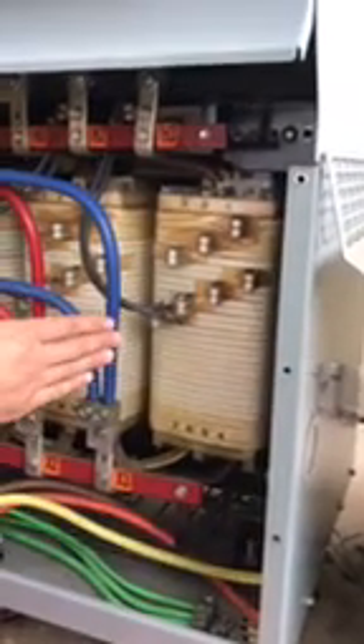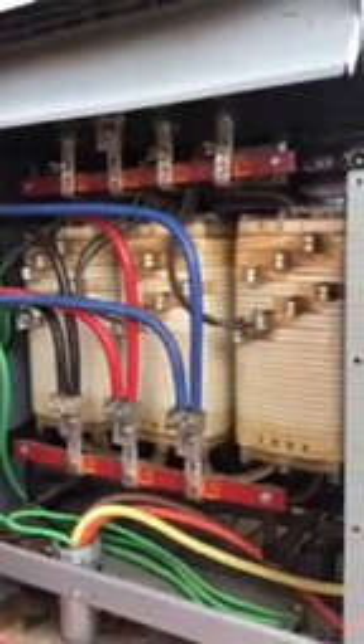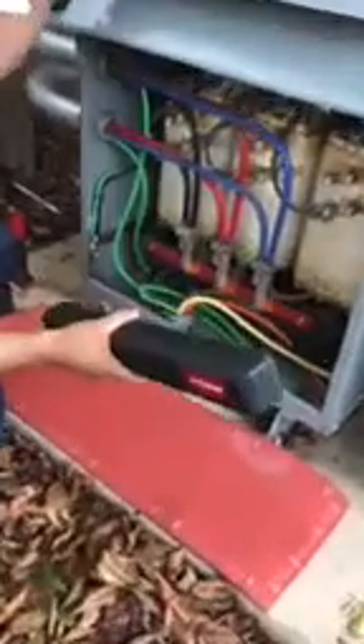But you have to do it for each coil, right? Because the step down, step up has to correlate to all the windings, and that's really it. It's just a matter of retapping that transformer. So this is what we mean when we say the transformer needs to be retapped. It's important to make sure that you torque these to the correct torque spec, because once you fire this up, you don't want any issues in here.